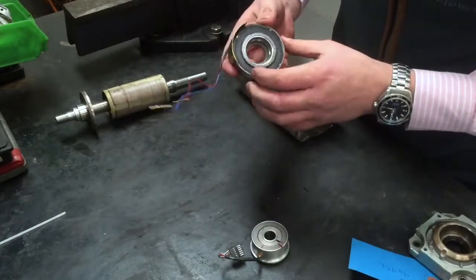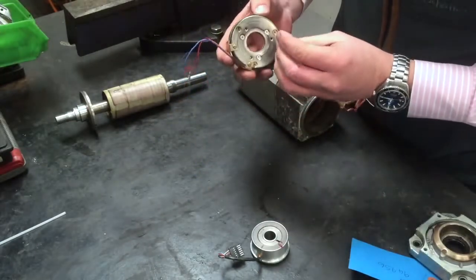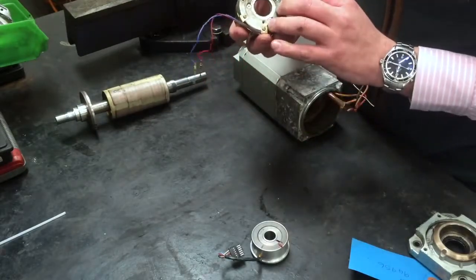This is the brake to the motor. We know that this operated satisfactorily, so we will strip the brake down, just confirm electrical tests, and give it an overhaul.